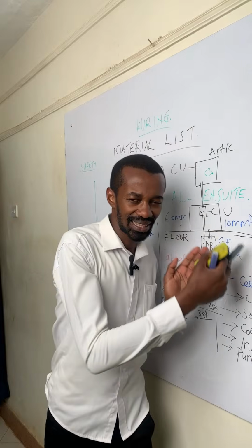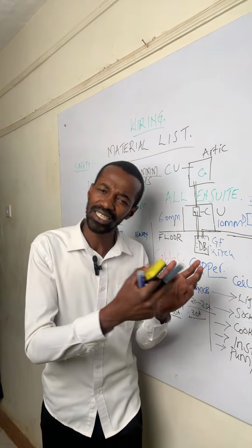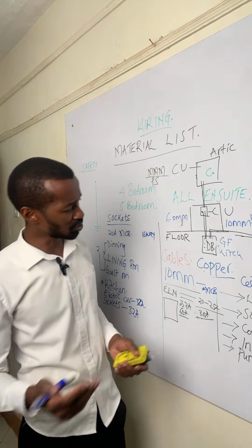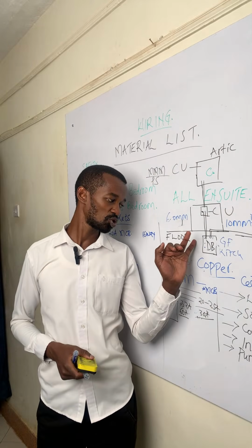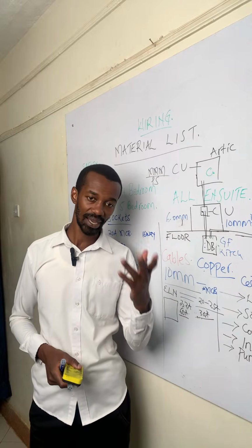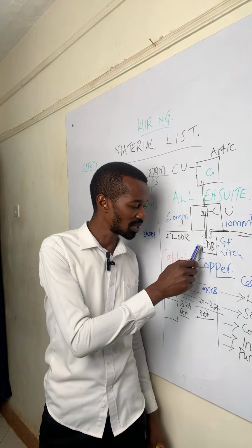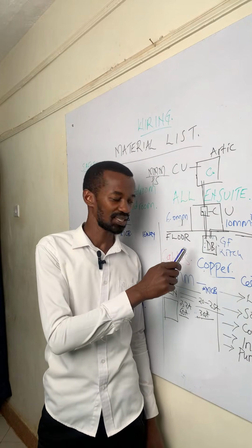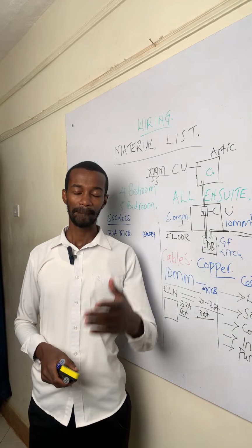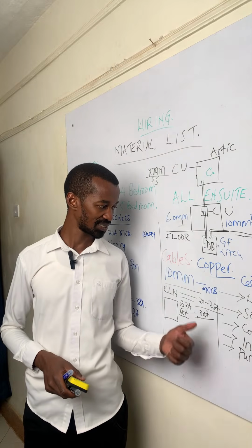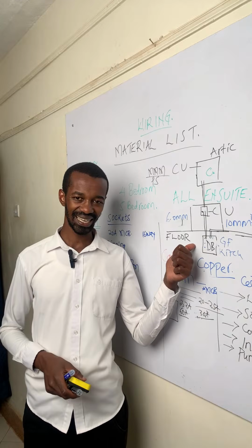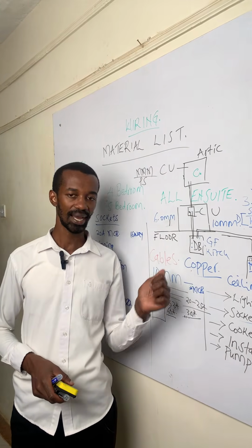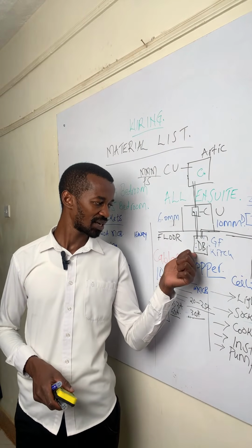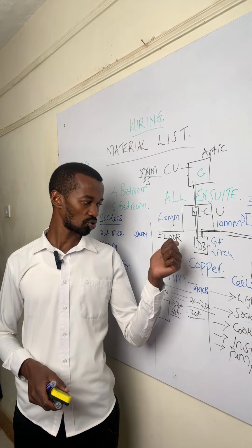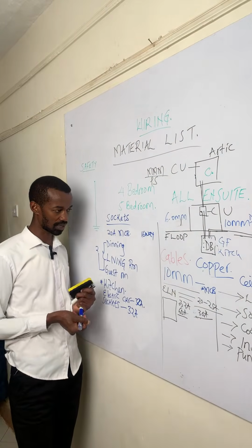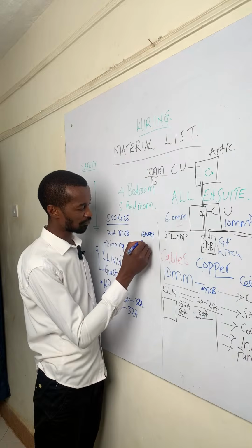So why would you have a three-phase distribution board in a single-phase installation? Many people will say a three-phase distribution board has a lot of provisions, and I agree, since we have allowances for the red phase, yellow phase, and blue phase. In other countries like USA and Canada, they don't refer to them as red, yellow, and blue, but as L1, L2, and L3 for the three phase. But why have a distribution board for three phase in a single phase installation? That is a waste. Instead, since you want a lot of provision, simply go with a single phase 16-way.